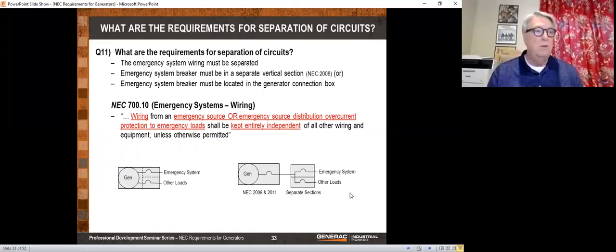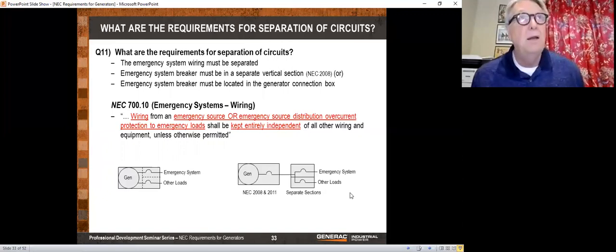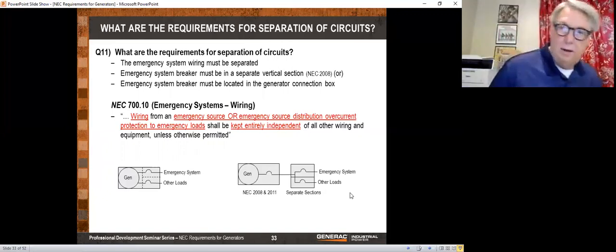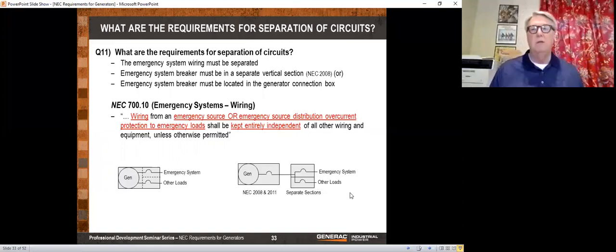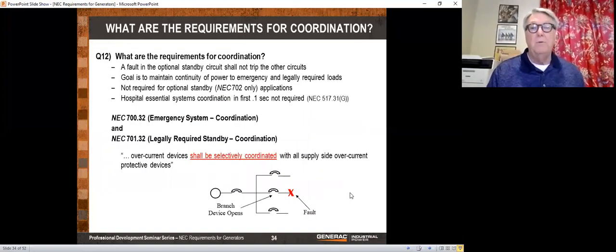If you have a generator that feeds a panel board or switchboard, and that panel board or switchboard then goes to some emergency loads and some other loads, you have to basically put your emergency circuit breakers in a separate vertical section from the other circuit breakers, and that's a pain, because you could have a 100 amp emergency circuit breaker, and it has to have its own vertical section. And I haven't seen inspectors who seem to know this, but I would be careful about that, because you don't want to have that rejected by the inspector. That was a new requirement.